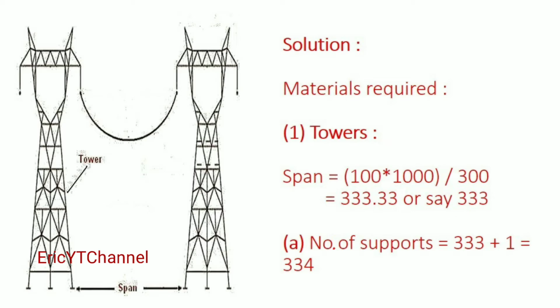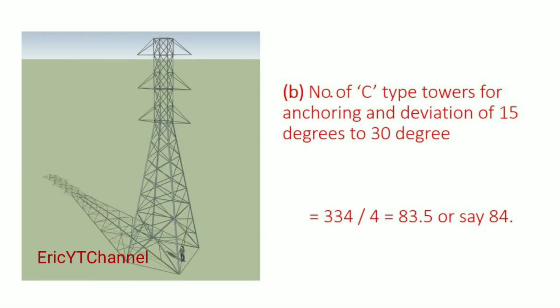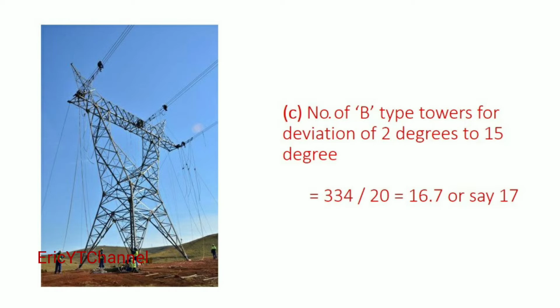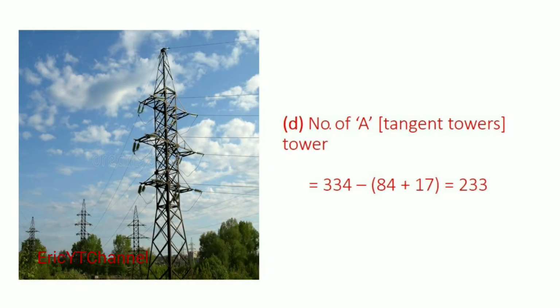Solution. Materials required. 1. Towers. A. Span equals 100 times 1000 divided by 300 equals 333.33, or say 333. Number of supports equals 333 plus 1 equals 334. B. Number of C-type towers for anchoring and deviation of 15 degrees to 30 degrees equals 334 divided by 4 equals 83.5, or say 84. C. Number of B-type towers for deviation of 2 degrees to 15 degrees equals 334 divided by 20 equals 16.7, or say 17. D. Number of A tangent towers equals 334 minus (84 plus 17) equals 233.